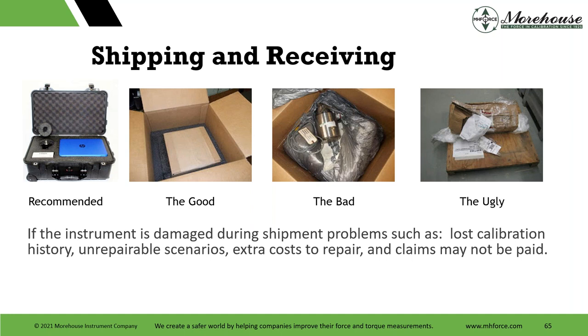I would suggest investing in better shipping cases, especially if you've had some damages. Evaluate your risk as the standard requires. Then if you're sending stuff out to the supplier, it makes it so much easier for your reference standards to go out in these cases. The good here is a double boxed set. And then we have the bad, like this custom blow foam, heavy load cell and cable. We see a lot of sheared cables in this scenario.